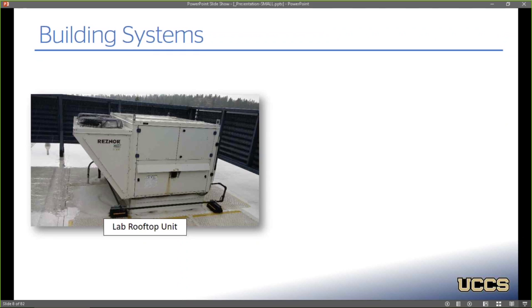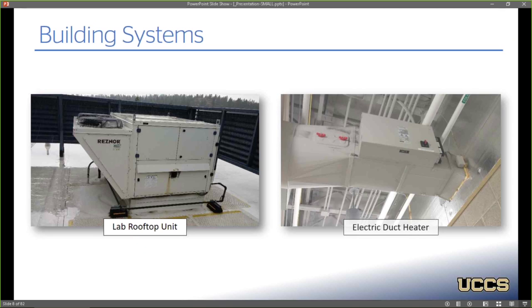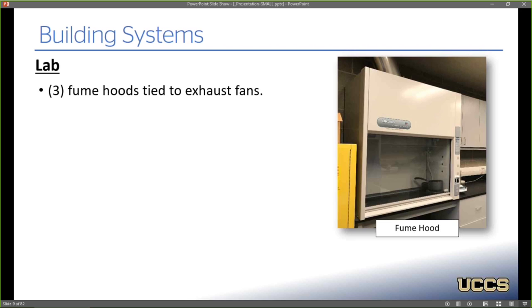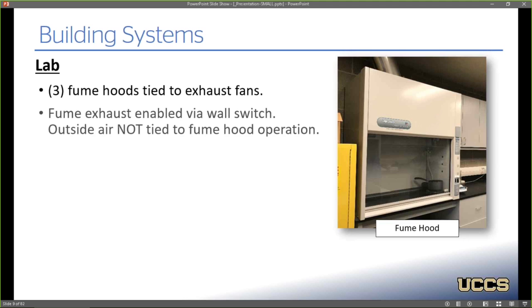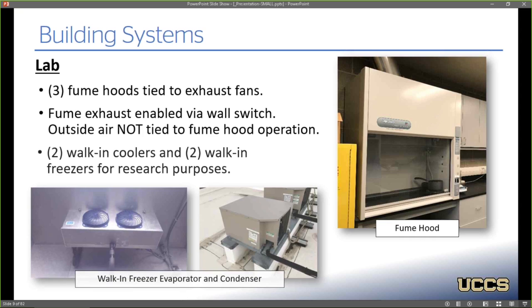This picture of that lab rooftop unit, strangely, it actually looks like it's in worse shape than the office equipment, which is actually older. And then one of the electric duct heaters inside, and everything inside is just exposed. Now at the lab, they have some unique systems. They do have 3 fume hoods that are tied to exhaust fans, but they're enabled via a wall switch, and the outside air from the rooftop unit, I mentioned it's constant volume, is not actually tied to any fume hood operation. And they also have 2 walk-in coolers and 2 walk-in freezers that they use for various research purposes and storage.